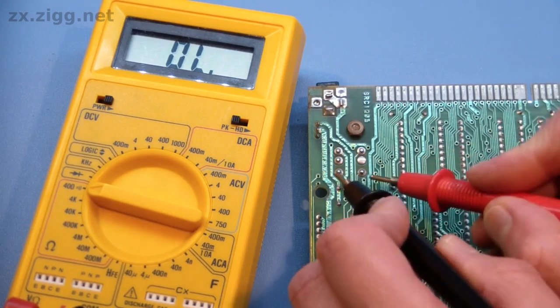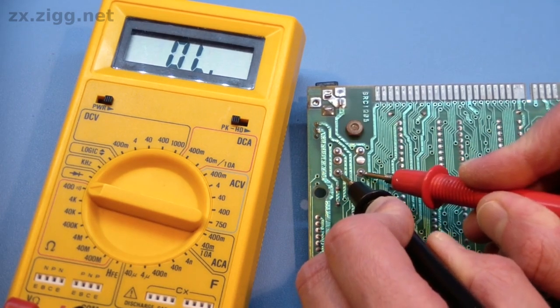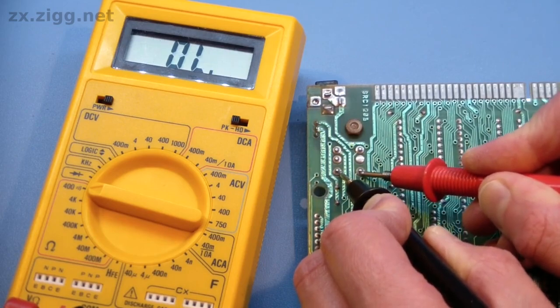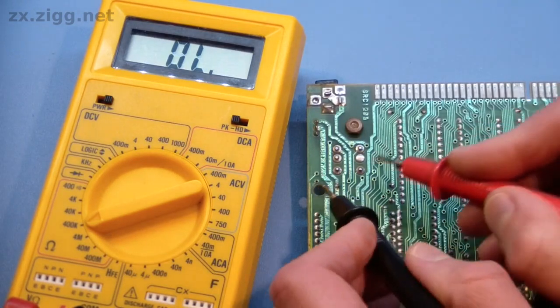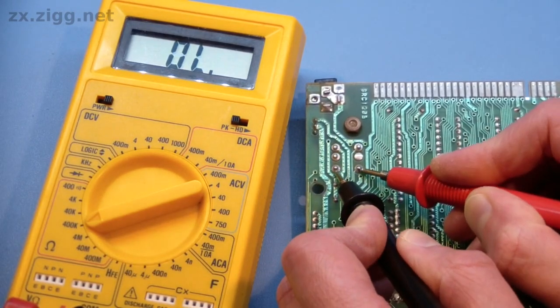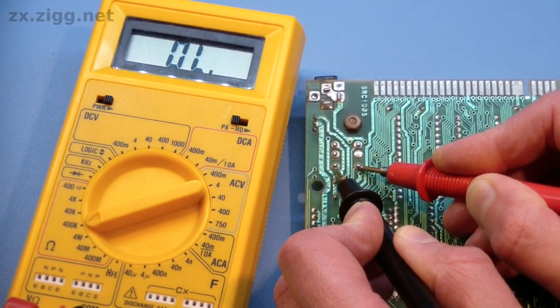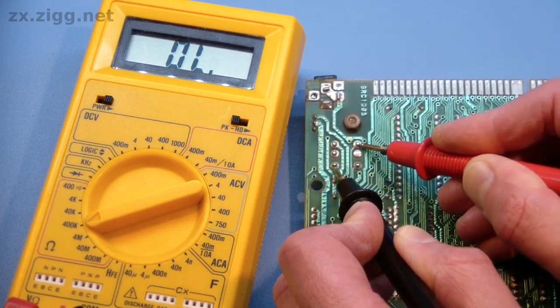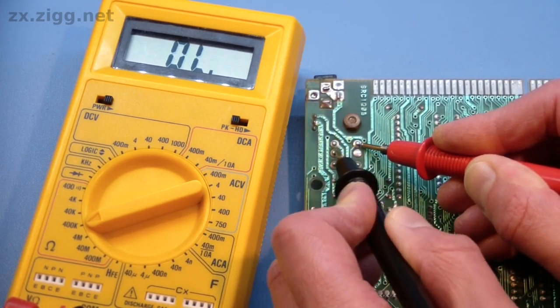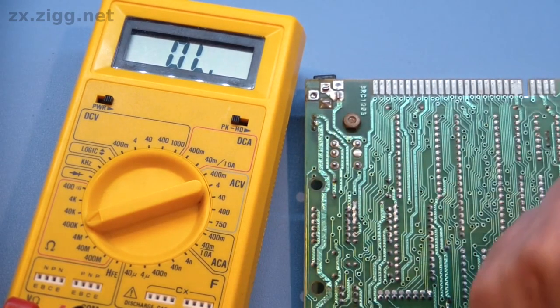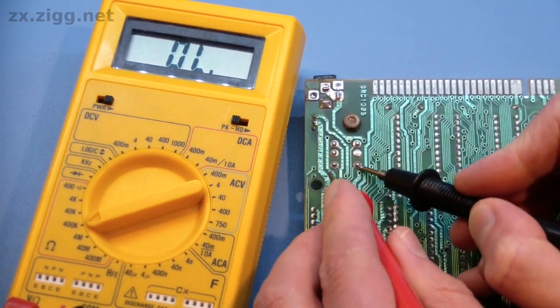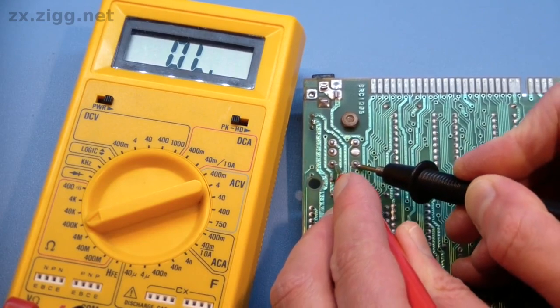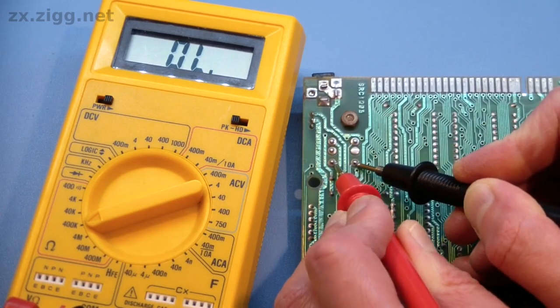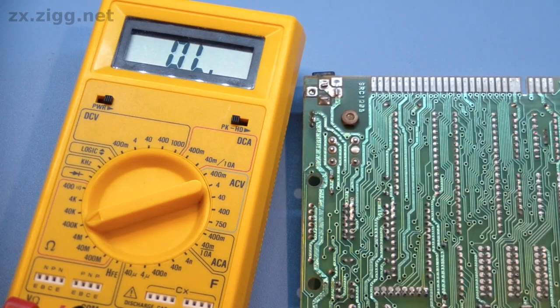Now check the resistance between the 2 windings. The meter should indicate open circuit or a very high value of at least several megohms. Because the windings are inductively coupled, you may briefly see some other value when you first connect the probes. Ignore this. Try with the probes the other way around too. Any low reading here may mean the insulation on the windings has failed and they have shorted together, but it's more likely transistor TR4 has failed with the short between its collector and emitter.